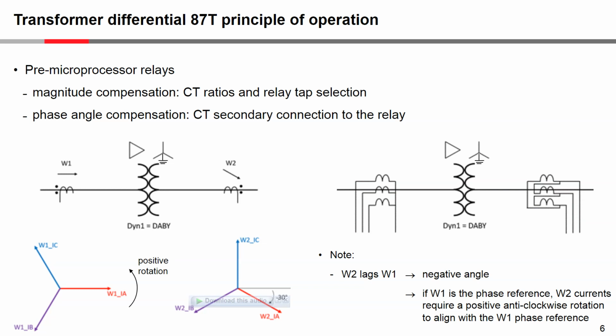But if you look at the Y side, you can see there you have a delta connection, and that delta connection of CTs is the same as the delta connection of the actual transformer. And what that does is rotate the current. So the output from the delta connection of the CTs, the current that would be connected to the relay, would have its phase rotated by the required angle. In this case, because it's a DY1 transformer, it would be anti-clockwise 30 degrees to align with the phase reference side.